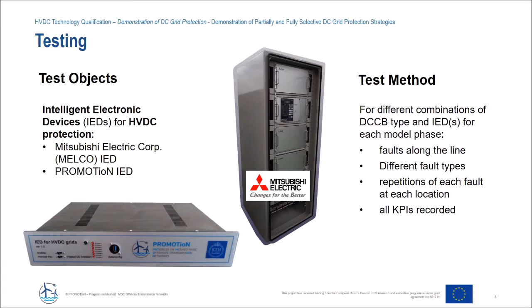I don't have time to go through the full results, but here's an example from some of the partially selective testing that we did, with just the single breaker and IED in operation each time. You can see some example time domain results on the right, and at the bottom you can see the IED times for the full length of the line for all the different repetitions of the fault. So you can see that's well within the 2 millisecond target that I mentioned earlier. In each case, this was a single vendor, but we did this for each of the different breaker types with each of the IEDs in turn and saw a similar and adequate performance throughout.